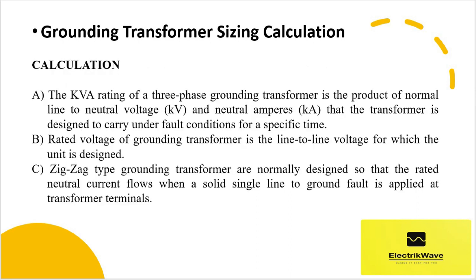Now let's see the calculation steps. (a) The kVA rating of a three-phase grounding transformer is a product of the normal line-to-neutral voltage (kV) and neutral amperes (kA) that the transformer is designed to carry under fault conditions for a specific time. (b) The rated voltage of the grounding transformer is the line-to-line voltage for which the unit is designed. (c) Zigzag type grounding transformers are normally designed so that the rated neutral current flows when a solid single line-to-ground fault is applied at the transformer terminals.